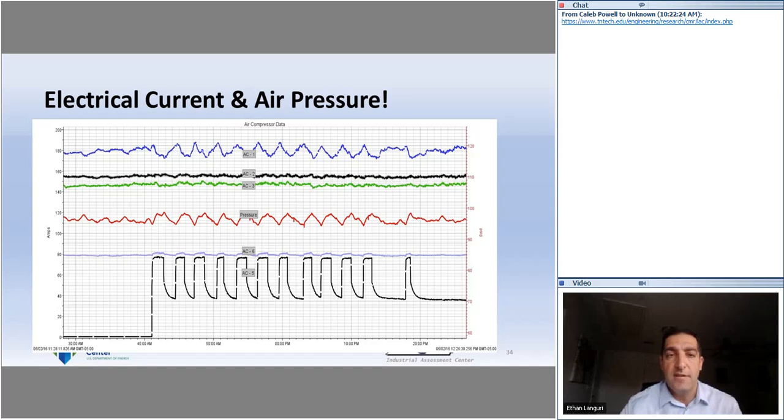And maybe this is also trimming, while it almost looks like base loading as well. So really this helps us as you zoom in and study this: do we have enough storage in the plant to compress air? If we don't have enough storage, we see a lot of quick back and forth load unload here. Maybe with some storage we get a longer buffer, as we have a larger storage, so our load unload doesn't work as hard. Or do we have a good control mechanism to have a number of machines as a base load and one, maybe only the best one, for our trimming? Maybe the best one could be a VFD machine, not the load unload one, and everything else. So this gives us a lot of information to really talk about our pressure, especially what happened at different times of the day when we have a peak and we have a low in pressure.